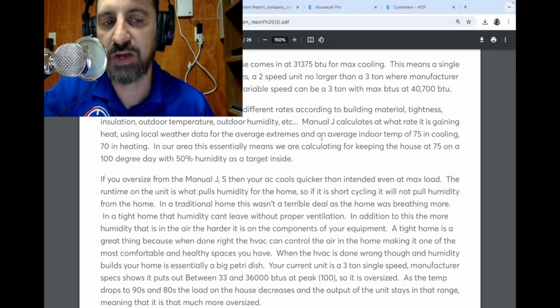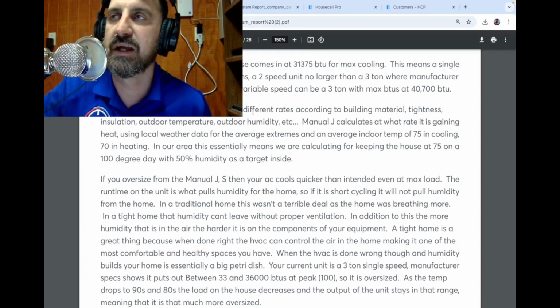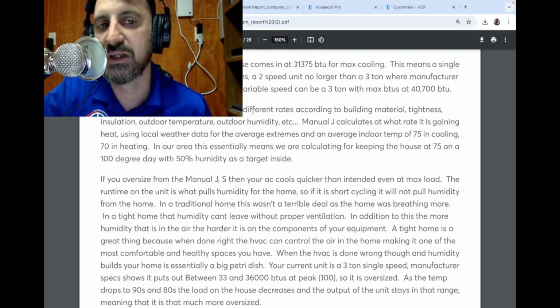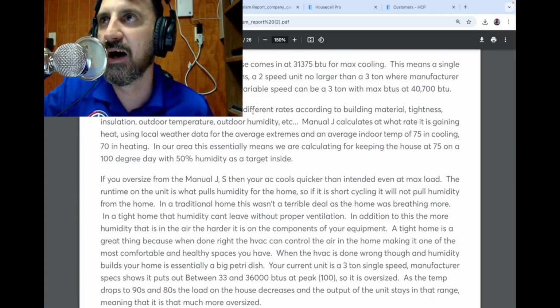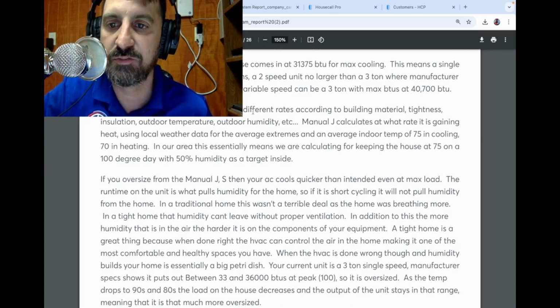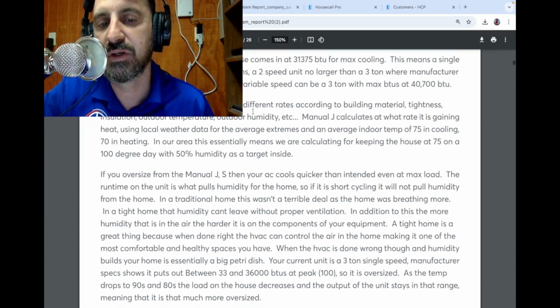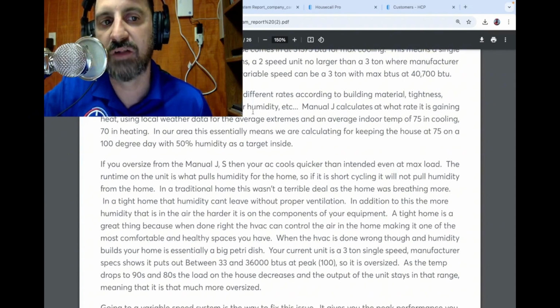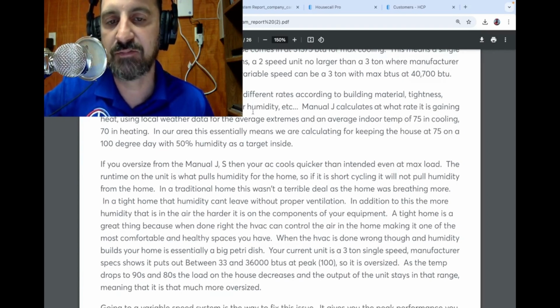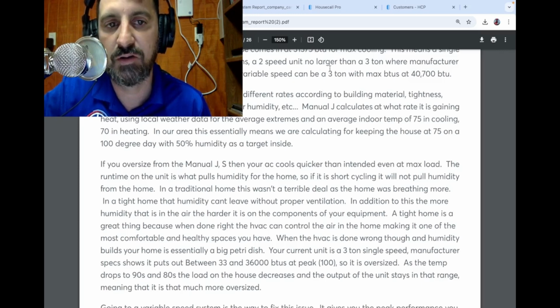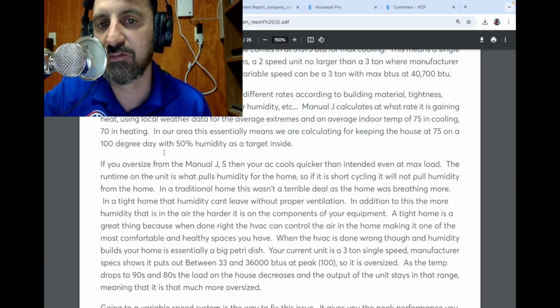Essentially, that's going to be oversized unless you're on like a 105-degree day, maybe you need 36,000 or whatever. But most of the time with a variable speed, it's something like 85 or 87% of the time you don't need your peak load. That's why sizing these ACs for peak load is really sizing them for like 10% of the year. So keep that in mind as we go through this. So the variable speed allows your unit to run less than that if it needs to, or get up to that if it needs that. In this home, variable speed running at that 40,000 will never run high speed.